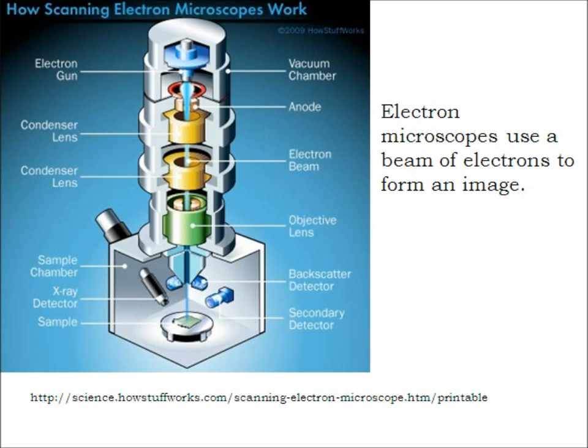So here's a cutaway of what the inside of our electron microscopes look like. This is not exactly ours, but it's going to be very similar inside. Essentially what we have is an electron gun up here, which we're going to induce to send a beam of electrons down to our specimen down here in the chamber. And to focus that specimen, we'll be using a series of electromagnets. Now we can't use glass lenses like you find on a regular microscope, because the electron beam won't go through glass. But the electrons have a charge, which means that they're influenced by magnetic fields. So these rings right here, these condenser lenses if you will, are actually just electromagnets. And the idea is to get those electrons finally focused right down here on the sample.